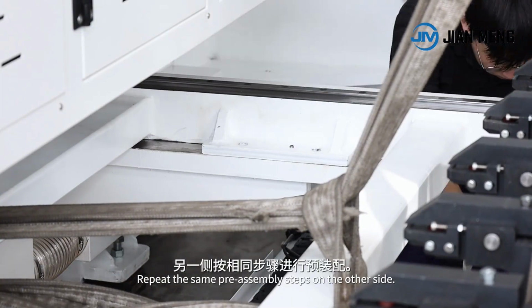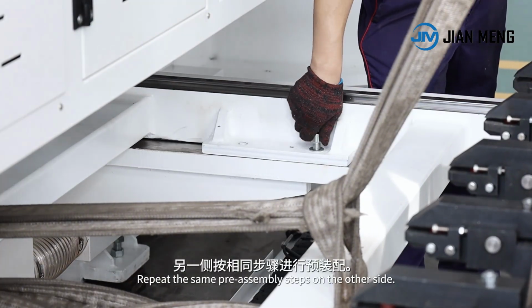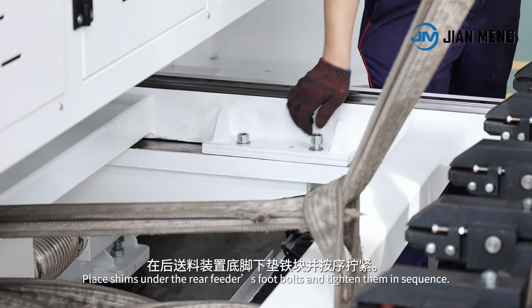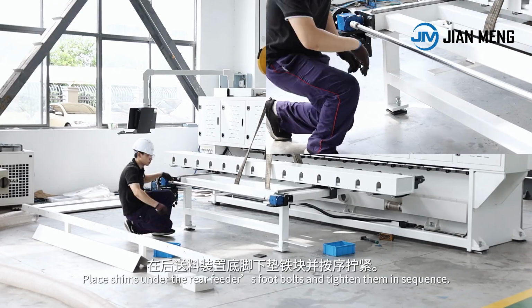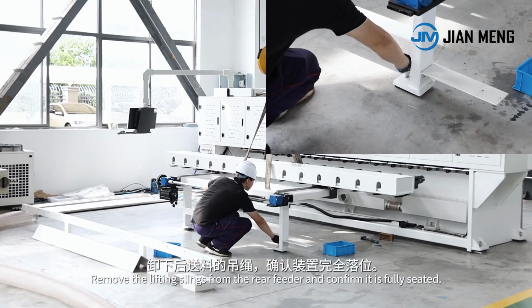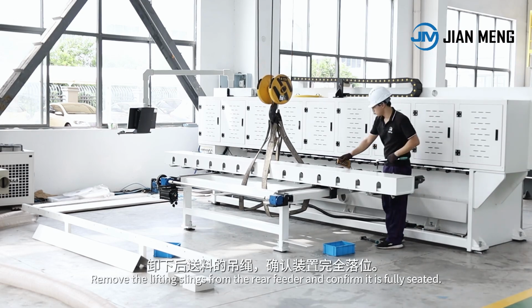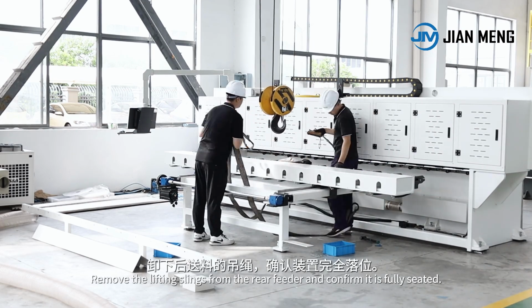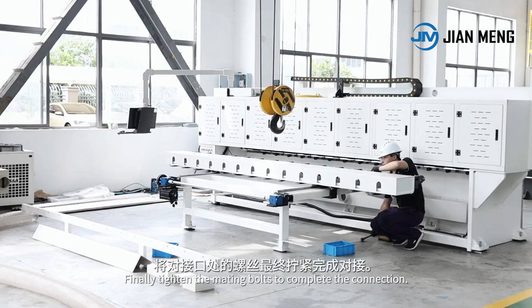Repeat the same pre-assembly steps on the other side. Place shims under the rear feeder's foot bolts and tighten them in sequence. Remove the lifting slings from the rear feeder and confirm it is fully seated. Finally, tighten the mating bolts to complete the connection.